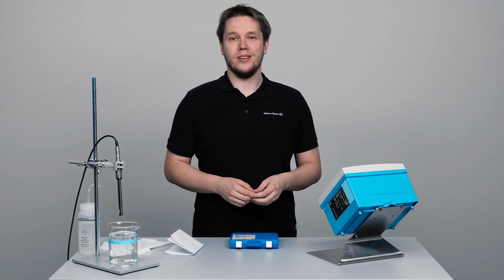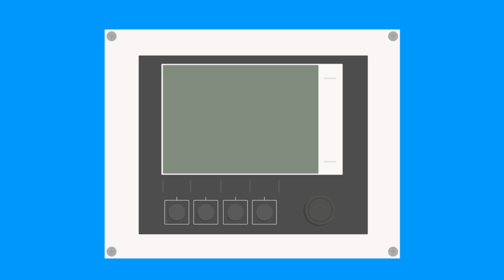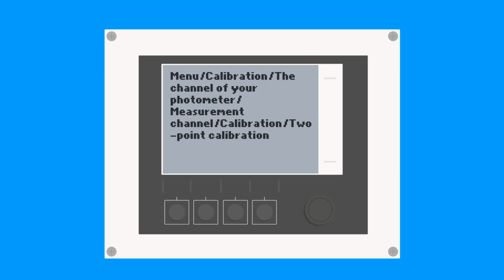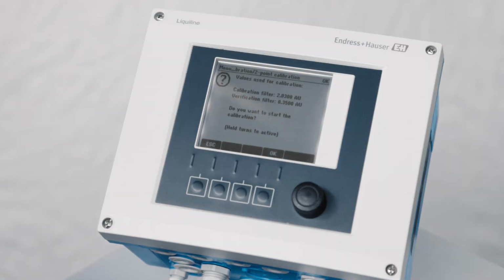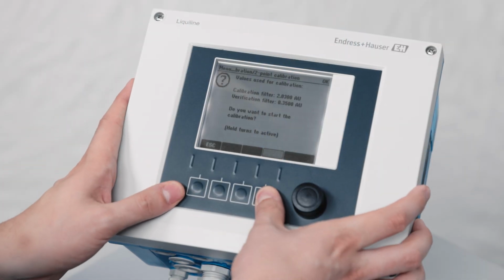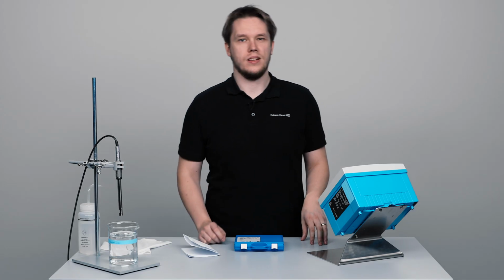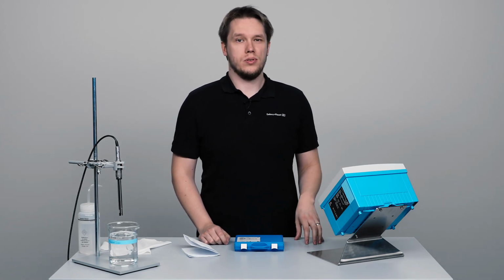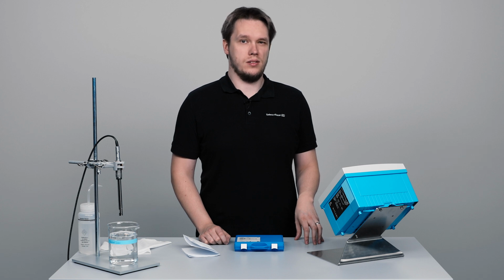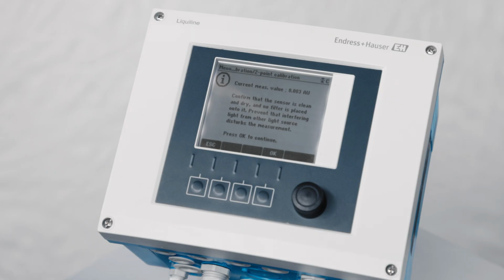Switch to the calibration menu and start the two-point calibration. Double-check if the filter values are set correctly and press OK. Leave the sensor in air, protected from any disturbing light sources, and wait for the signal to get stable. Press OK.